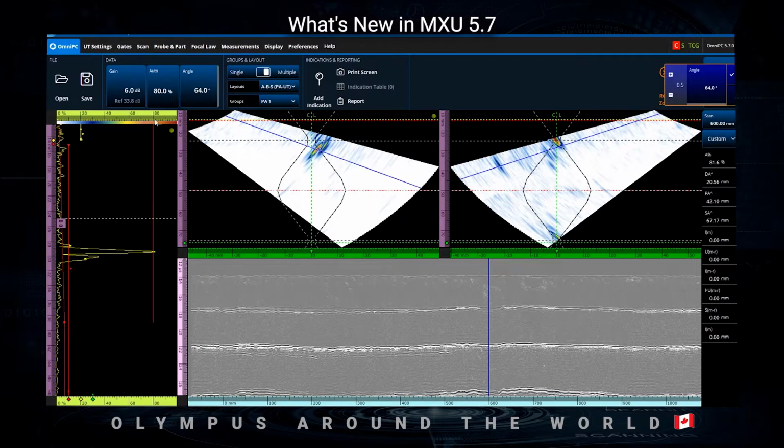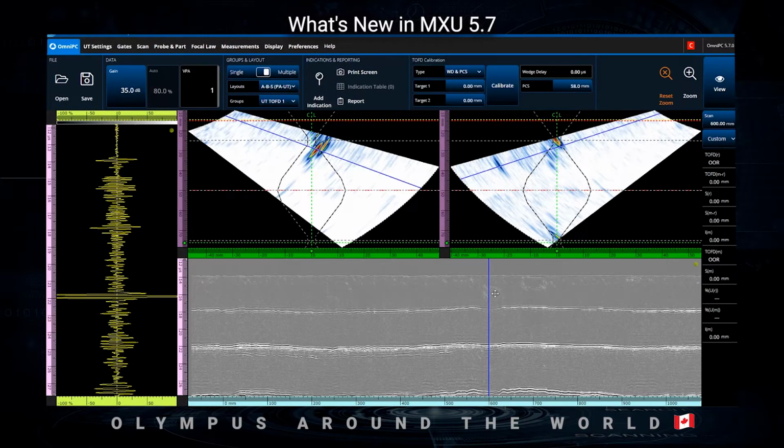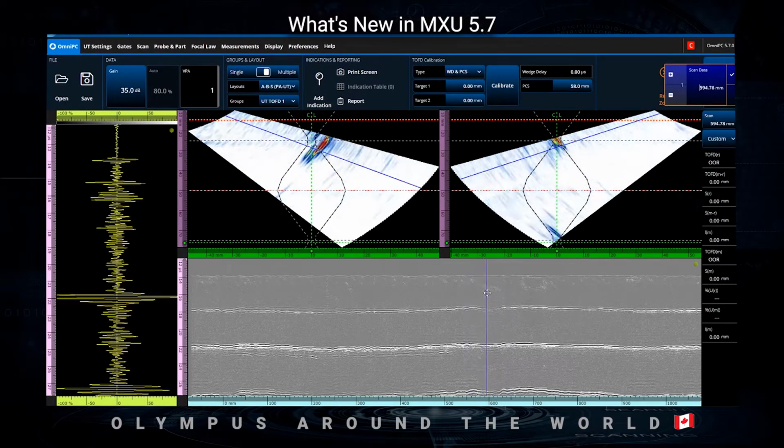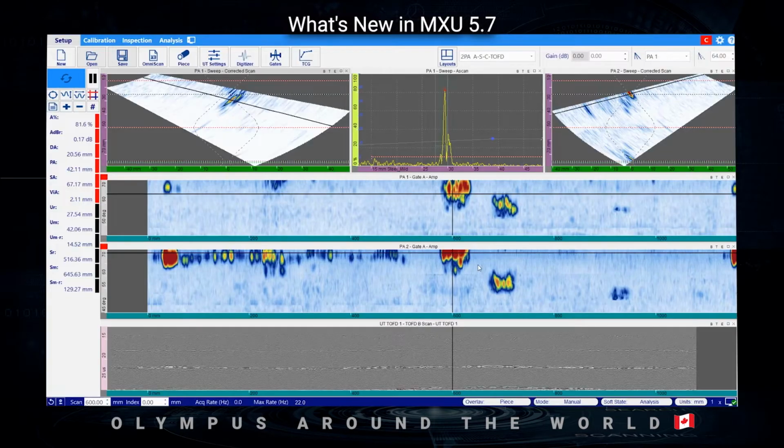Benefit from the new additions. In this example, software gain, which was not available with the MX2. You can lower the gain, increase the gain, move from one group to the next. And compared to the old one, there's no longer a need for security dongle or hasp. It's free of charge. It's only a download away from benefiting from this. If you want more advanced features or more capabilities, WeldSight also supports legacy MX2 files now.